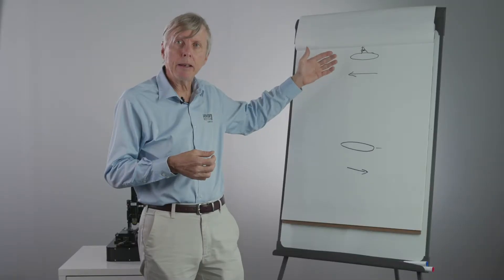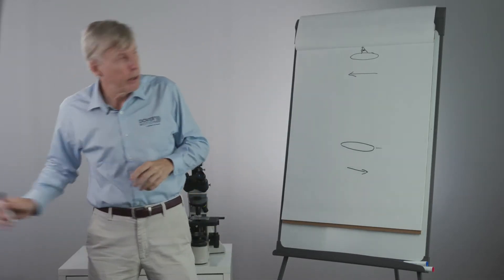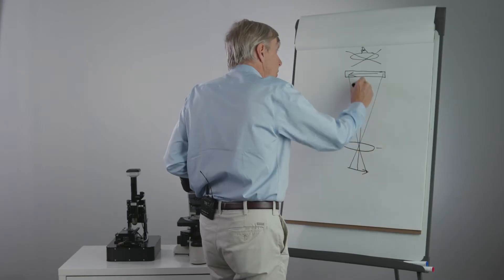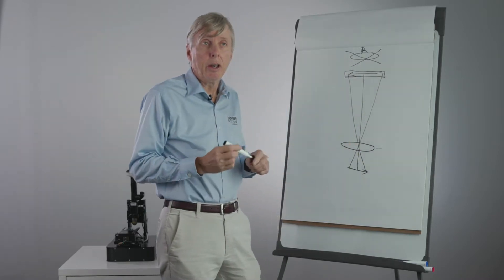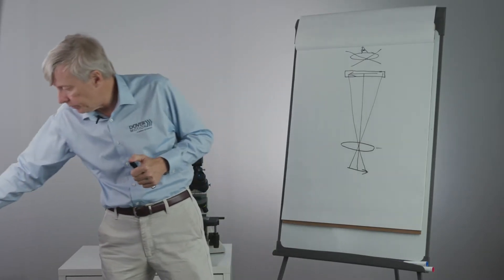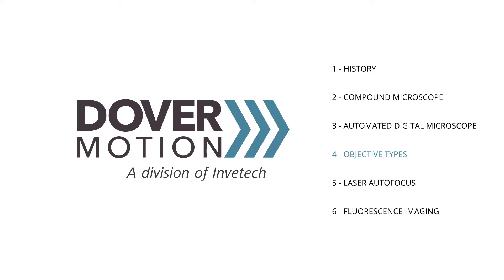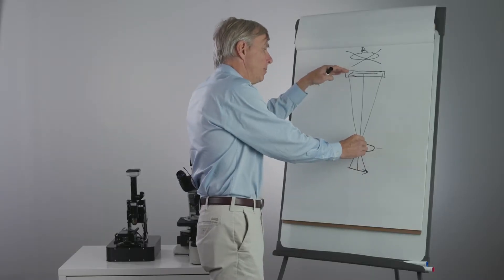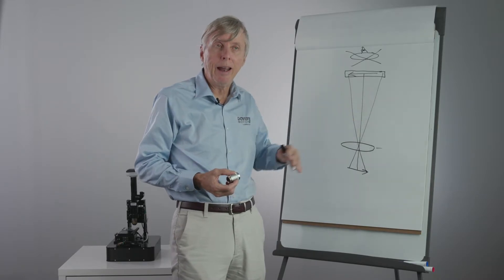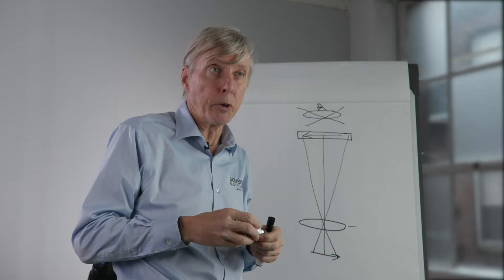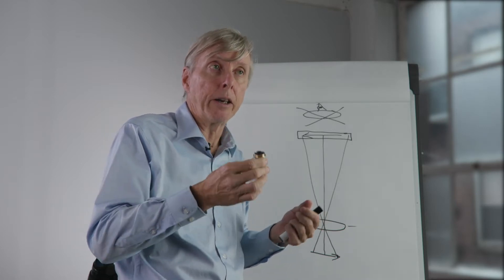It's important to point out that the eyepiece is not present in a digital imaging system. The imaging sensor is placed at the image plane, and light from the sample goes up directly to the imager with only a single lens — usually a fairly complex lens referred to as an objective. There are two basic types of objective. The first is finite conjugate: the objective images the sample directly onto the sensor plane. The issue is that for a variety of reasons we want to introduce additional optical elements above the objective, and with diverging light that is optically challenging.